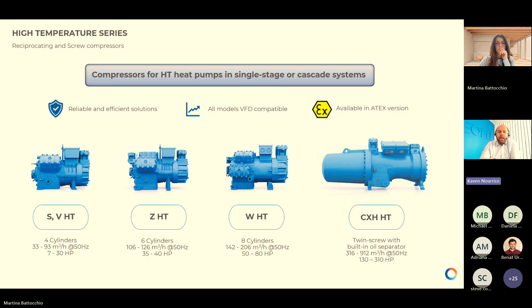As said, we have 2 steps of the development. The first one is to deliver water or fluid at 140 degrees with different refrigerants. It can be a natural refrigerant like hydrocarbons, or synthetic refrigerant like R-1233zd. With our range, we are able to produce up to 1 megawatt with this kind of system.